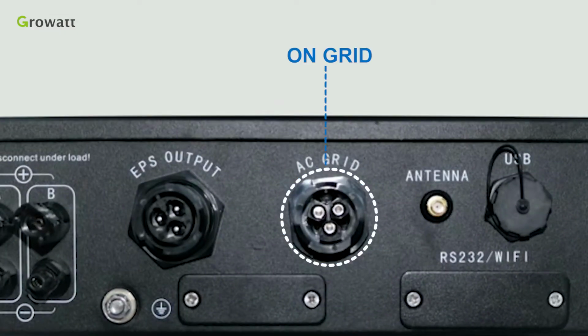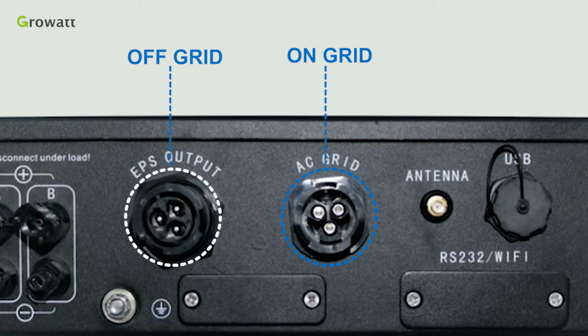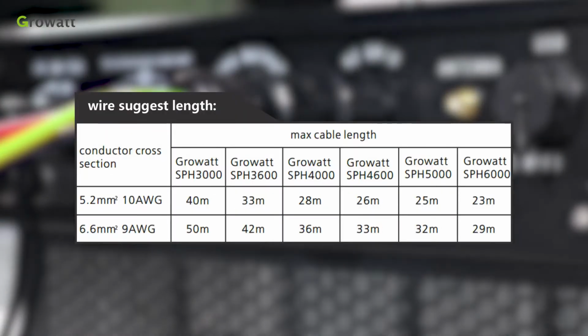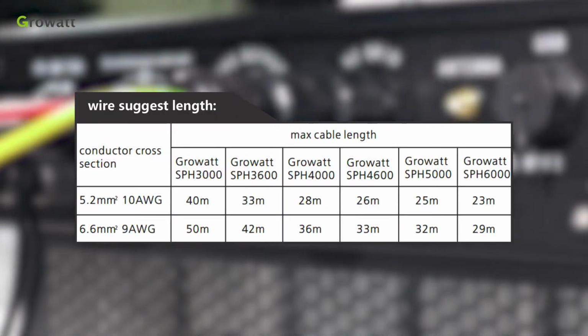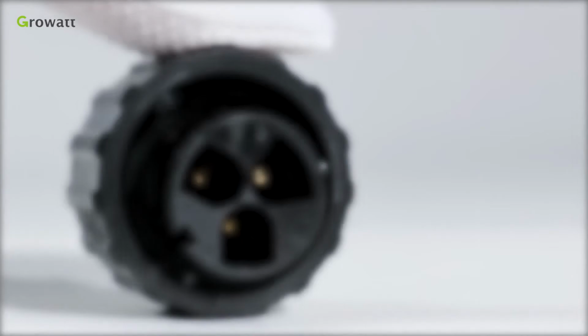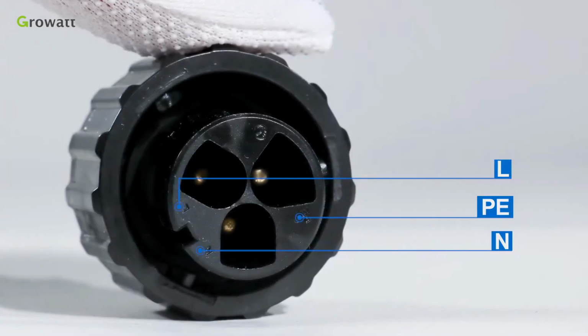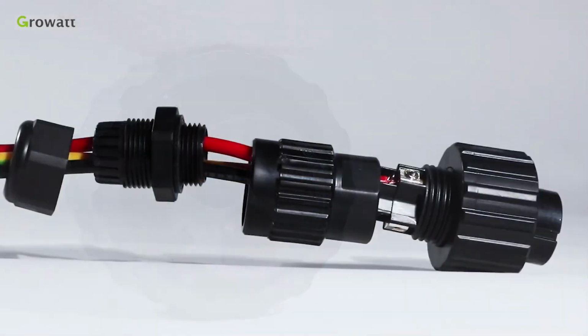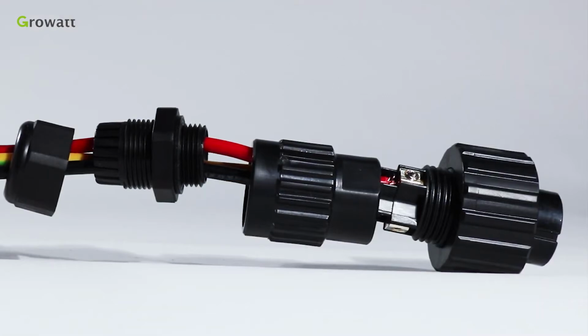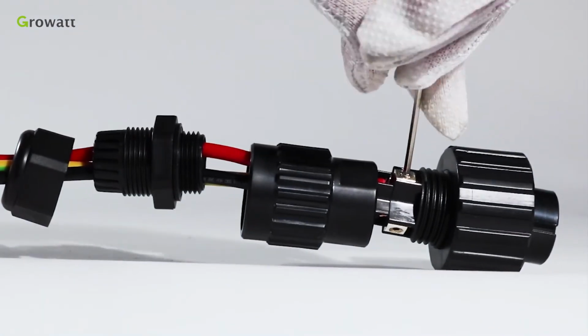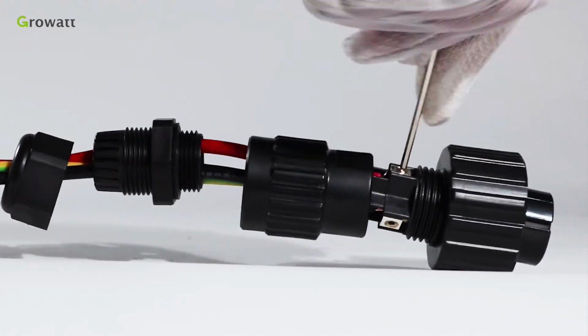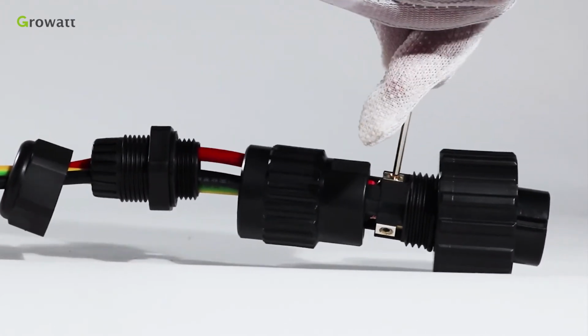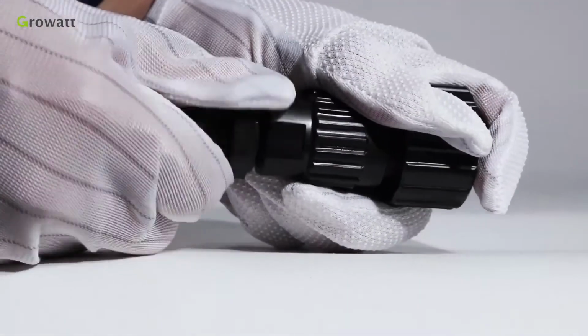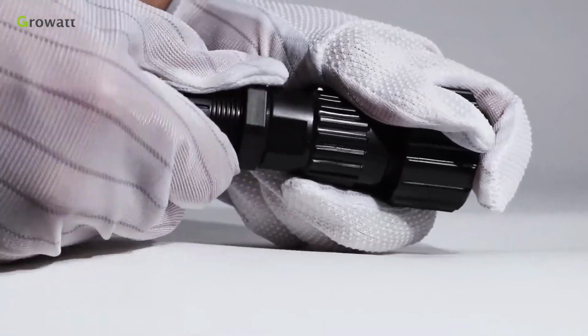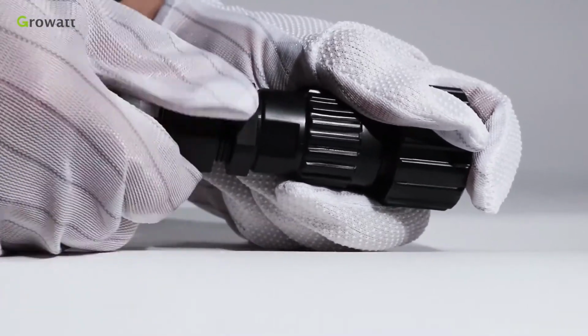SPH has an AC grid terminal and EPS output terminal. We can follow this AC wire suggestion to choose suitable cables. First of all, please confirm the L and PE port of the connection terminal and thread cables through pressure screw, seal ring, threaded sleeve in sequence. Insert cables into connection terminal according to polarities indicated on it and tighten the screws. Push and rotate the threaded sleeve onto connection terminal until both are locked tightly.